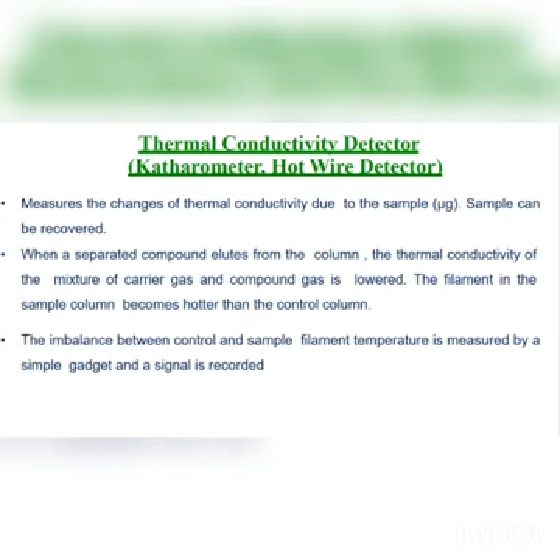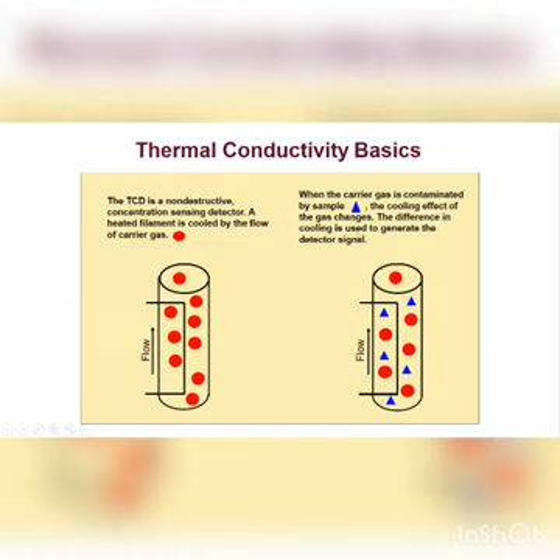Here in the first figure, a heated filament is cooled by the flow of carrier gas. When the carrier gas is contaminated by the sample, the cooling effect of the gas changes, which generates the signal. Here you can see in the figure, in the first figure only the carrier gas flows, so the filament temperature is low, while with the sample in the carrier gas, the difference in cooling is used to generate the detector signal.